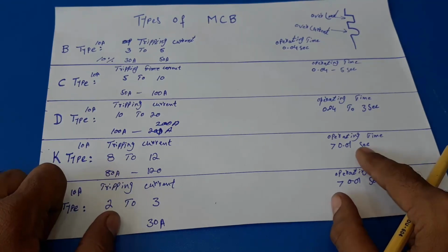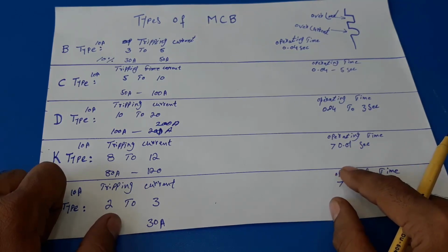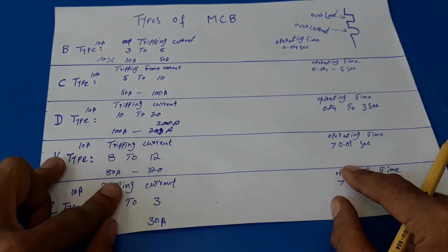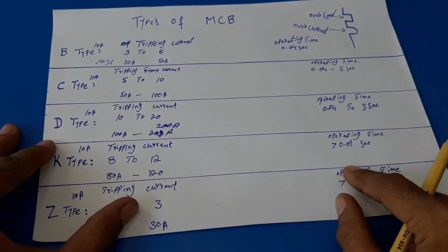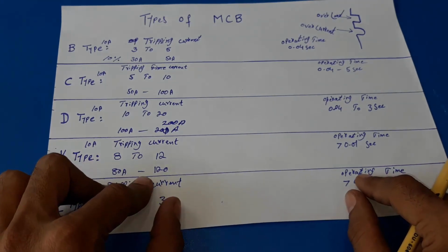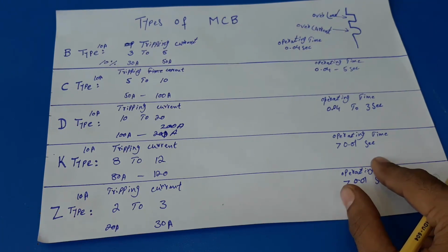K-type and D-type curve breakers are both designed for motor applications. The function of the K-type MCB is protection and control of circuits such as motors, transformers and auxiliary circuits against overload and short circuit. It also provides the best protection for cables and lines. Where do we use the K-type MCB? We use it in commercial and industrial use, meaning you have very sensitive circuits like PLC circuits and many other circuits in factories, homes or offices.